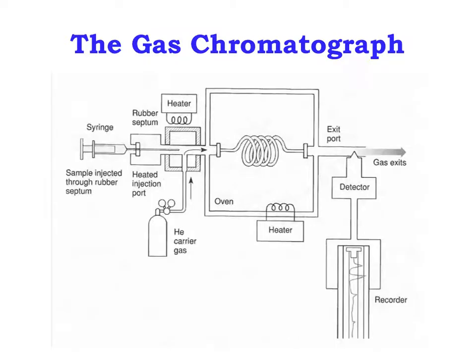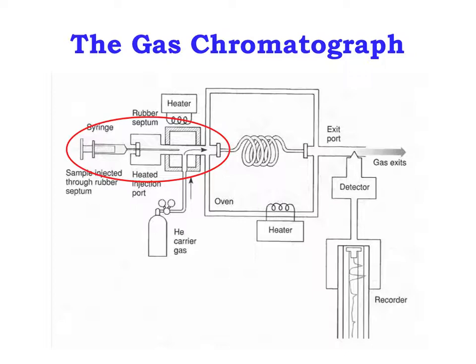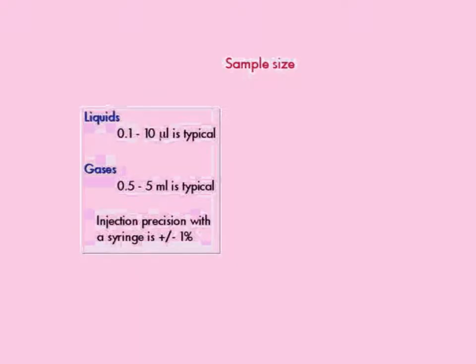This is a diagram of a gas chromatograph. Note that several components of the instrument are heated — they really are hot. Be careful not to touch them when you go into the instrument room. To begin the process, the sample is injected into the instrument using a syringe. Once the sample is volatilized in the heated injection port, it is mixed with the carrier gas and moves into the column. The sample size is typically very small, less than one microliter for liquids.